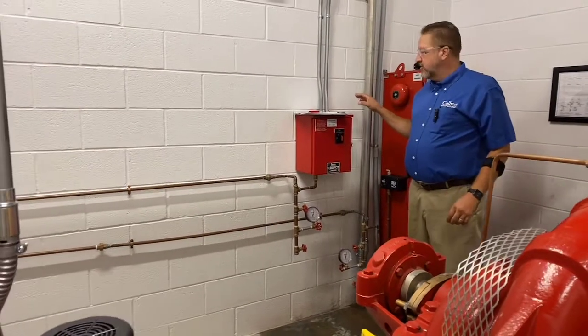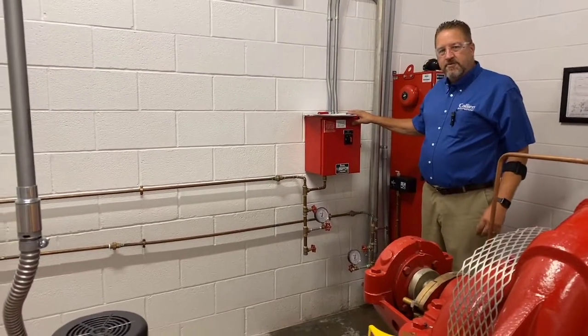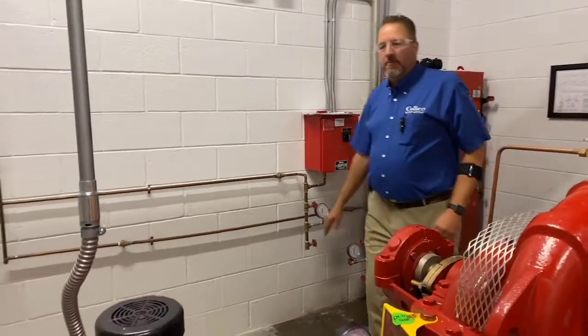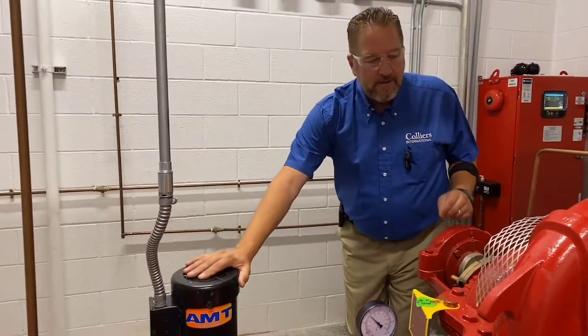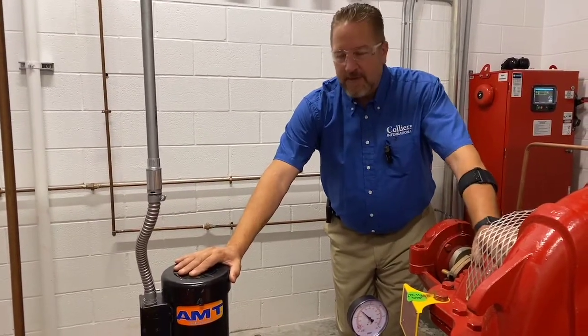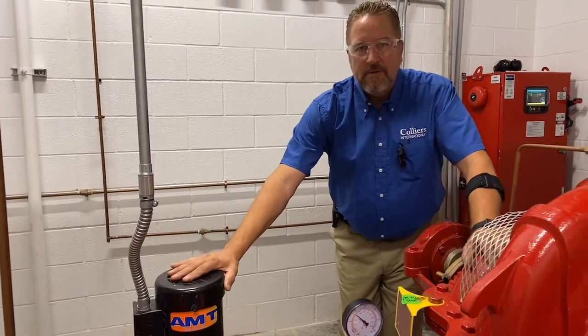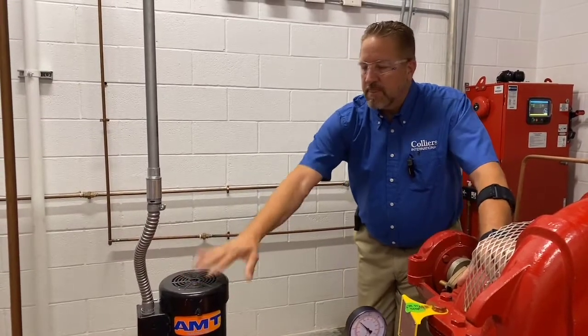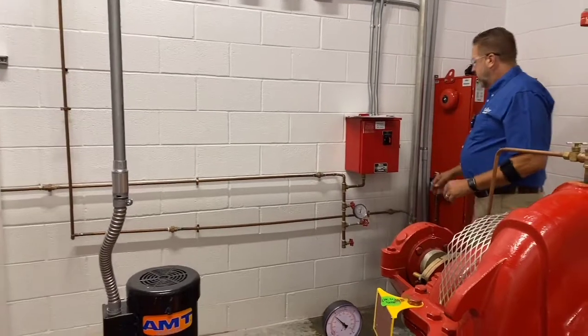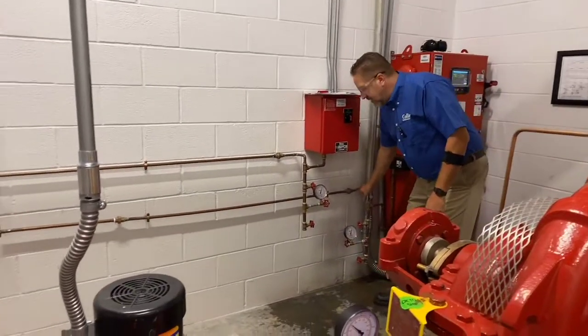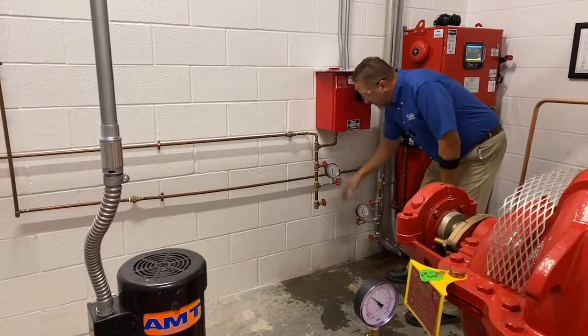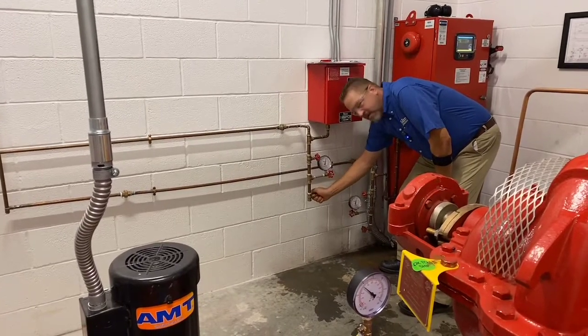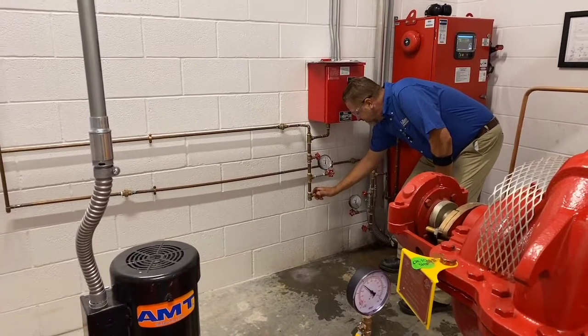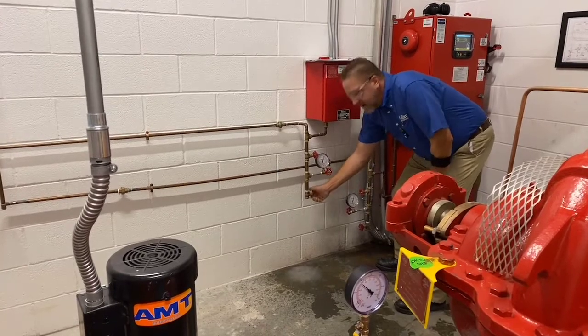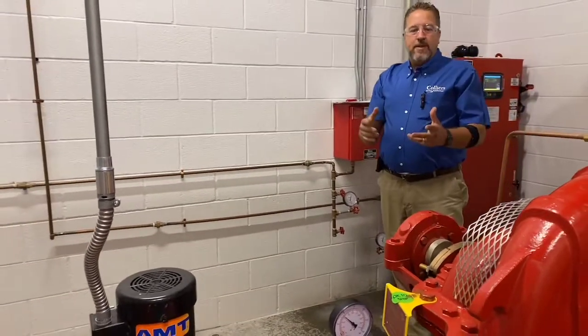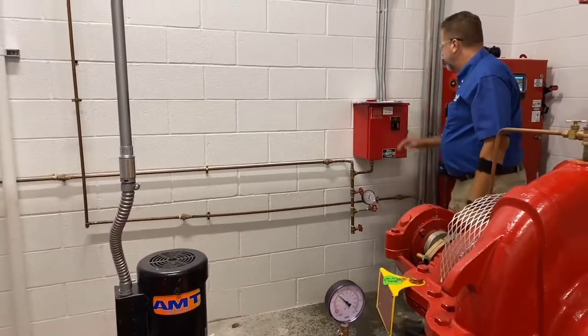Next, you're going to come over here and test your jockey pump controller and make sure it is working. Remember, the jockey pump is that little pump right here that runs, so this big pump doesn't have to. That's going to keep you at normal pressure readings. The way to test that is much like we did here with the pressure sensing line. You've got one here for your jockey pump, and it'll be quick. There you go. So that brought us back up in pressure, so I know that's working.